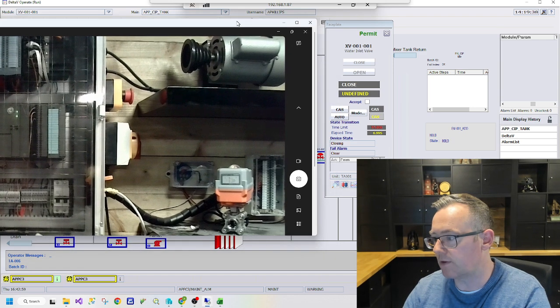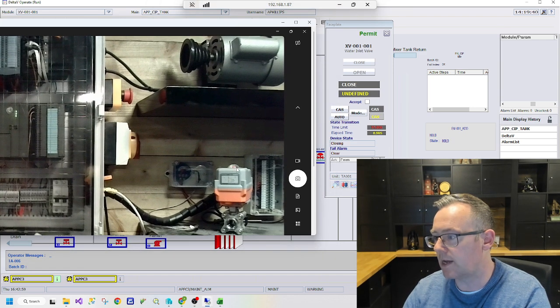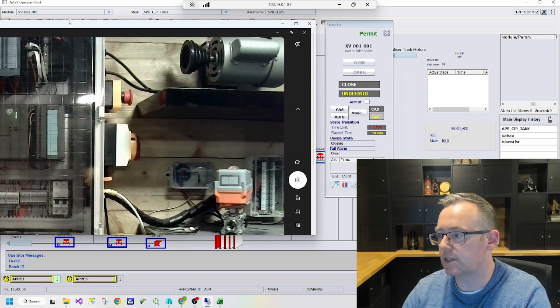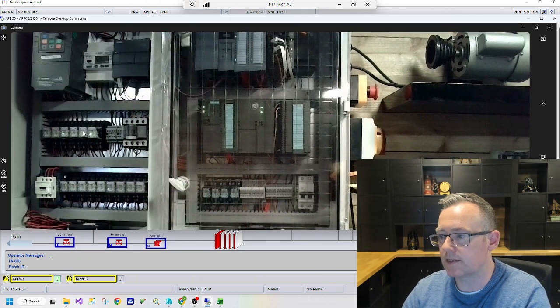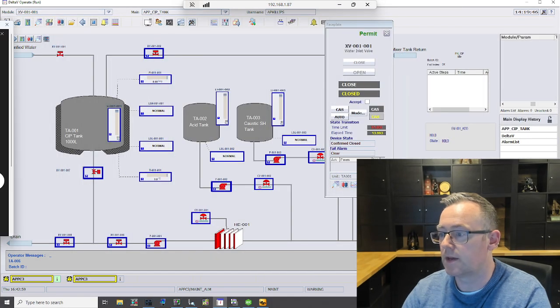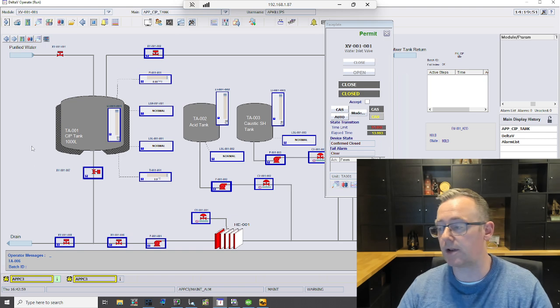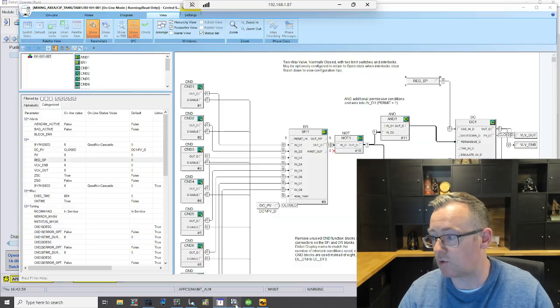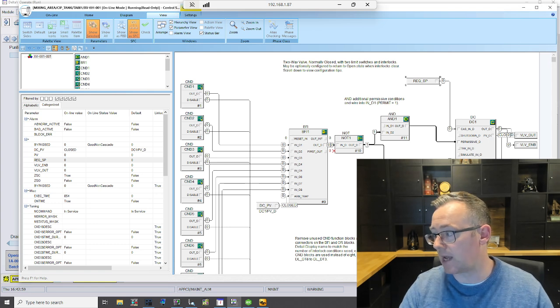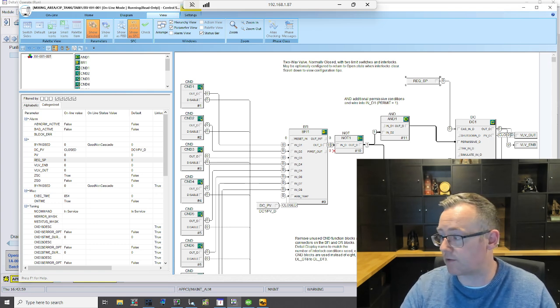Here I can see in real time it's going to go from yellow to red, and the second relay went off there. That's a practical example where I'm looking at these values having an impact in real time.